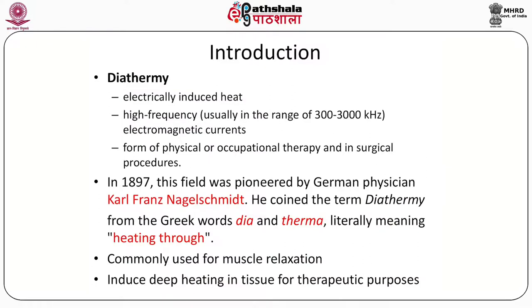To introduce the topic of diathermy — what is diathermy? In simple words, it is the electrically induced heat. To define it: diathermy is the use of high frequency, usually in the range of 300 to 3000 kilohertz, to induce electromagnetic currents as a form of physical or occupational therapy and in surgical procedures.